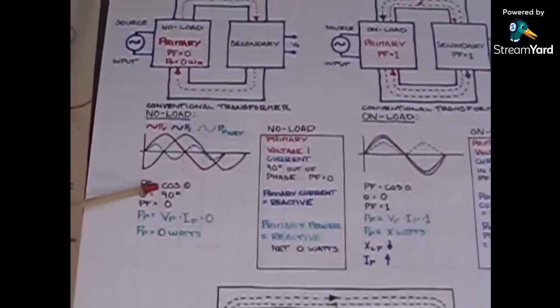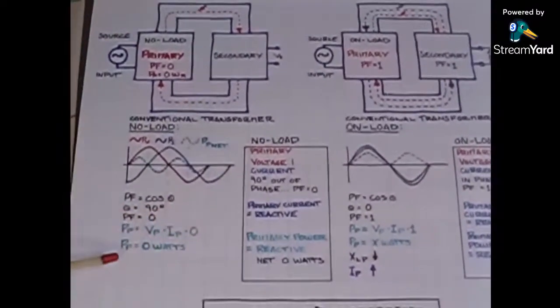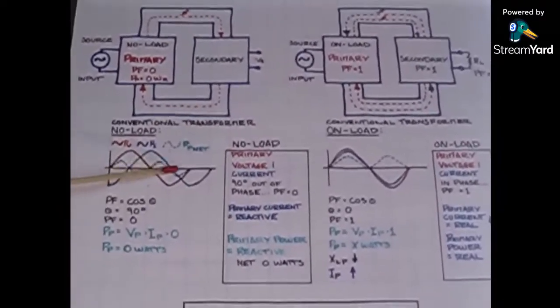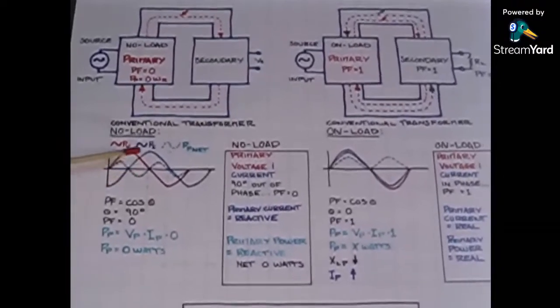So to go over just a little bit of transformer basics for you, here we have the conventional transformer that is on no load. There's no load connected to the secondary. The primary delivers flux to the secondary and induces a voltage in the secondary. The primary voltage and current are 90 degrees out of phase. That means the cosine of 90 degrees is 0, and the power in the primary is the voltage times the current times the 0, which is 0 watts. The power in the primary is evenly distributed, equally on the top and on the bottom, and this indicates that the incoming power on one half of the cycle is being returned on the other half.